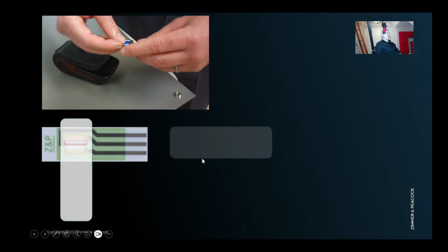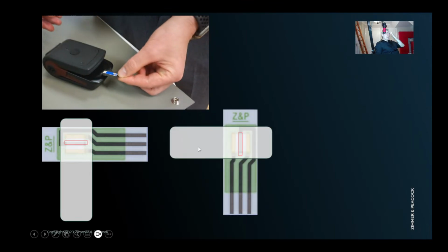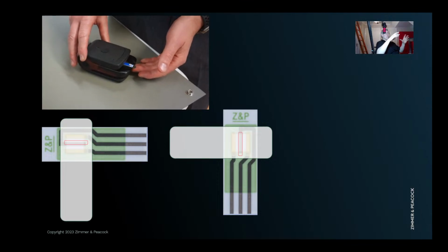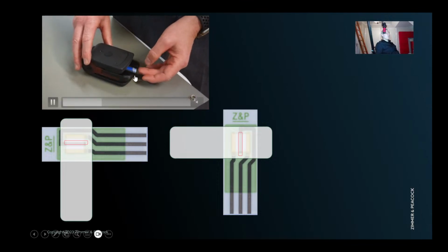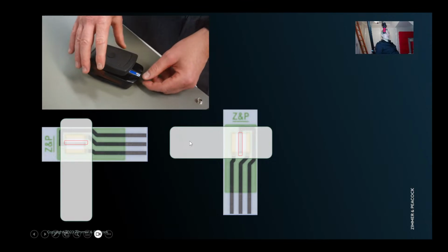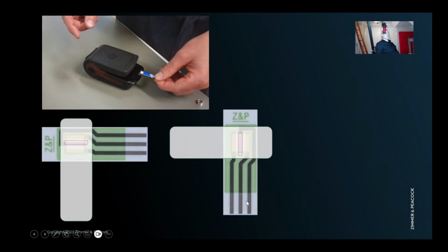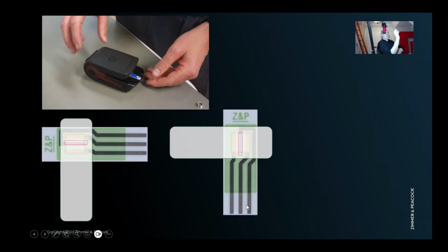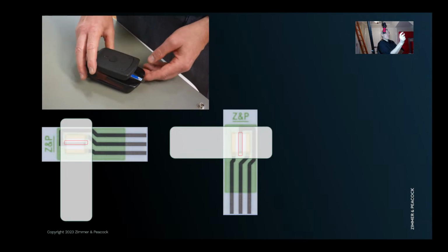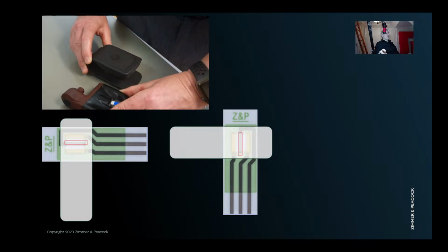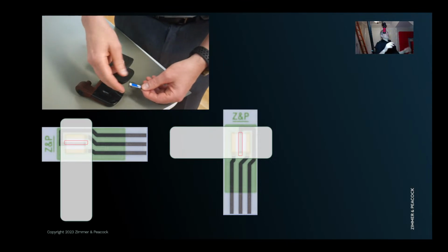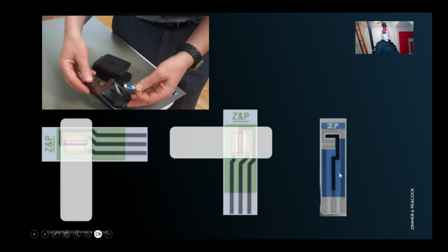The problem with coming in from the side like this is I think it makes for a very large footprint device, and it's actually quite an awkward little device because you've got the sample coming in here and the electrical connections coming in here. I actually think it's quite hard to then make a device to receive this device. So I would say don't do this, because I know the way I would design the device is this.